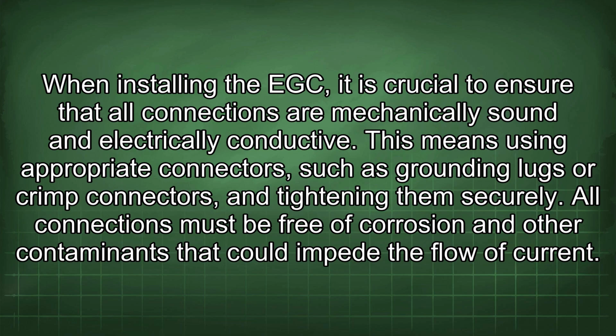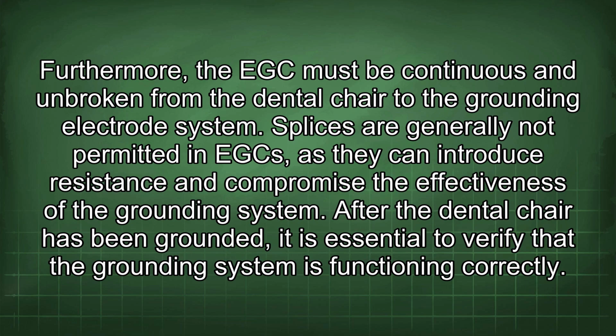When installing the EGC, it is crucial to ensure that all connections are mechanically sound and electrically conductive. This means using appropriate connectors such as grounding lugs or crimp connectors and tightening them securely. All connections must be free of corrosion and other contaminants that could impede the flow of current. Furthermore, the EGC must be continuous and unbroken from the dental chair to the grounding electrode system. Splices are generally not permitted in EGCs, as they can introduce resistance and compromise the effectiveness of the grounding system.